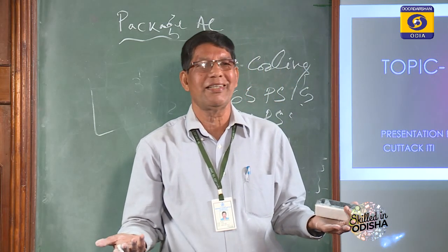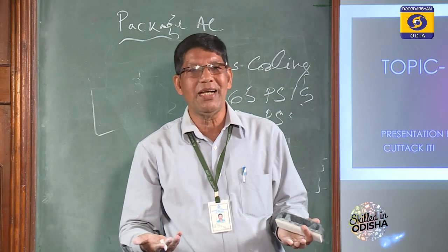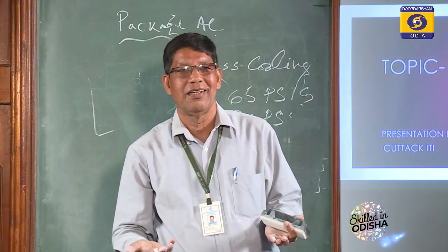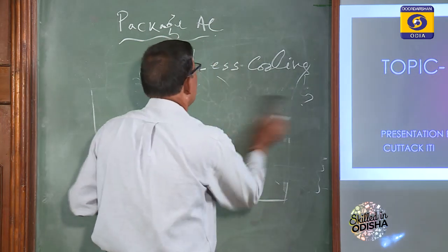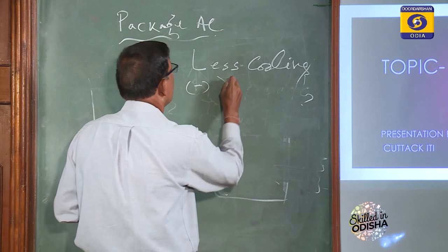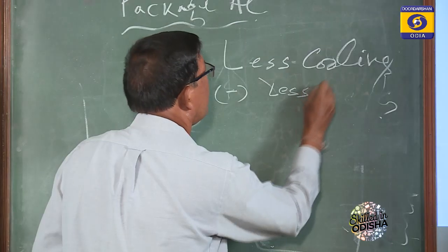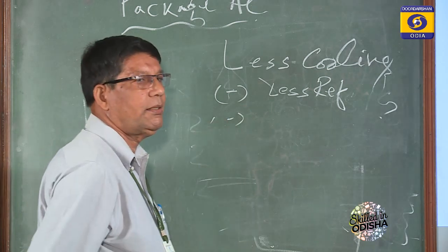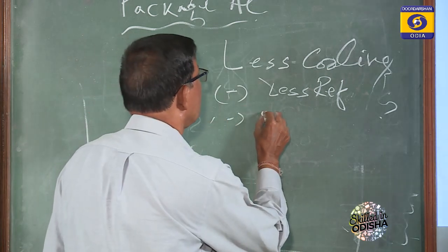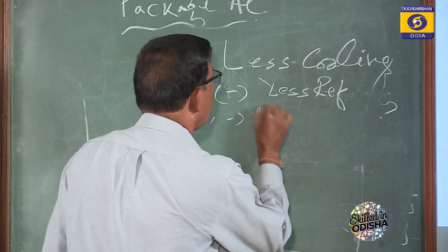It will not start. So for less cooling, the first cause is less refrigerant. Then the second cause is poor insulation.